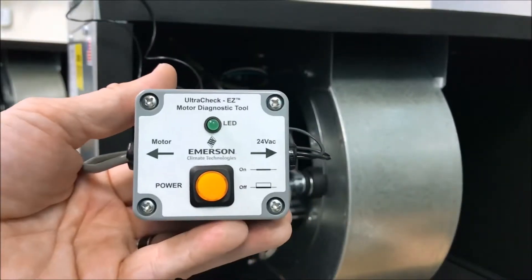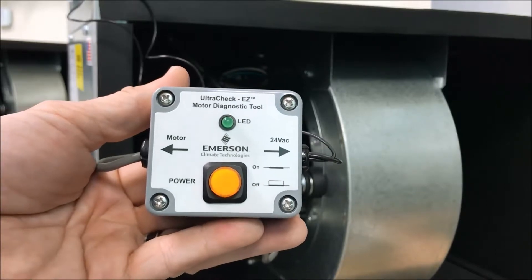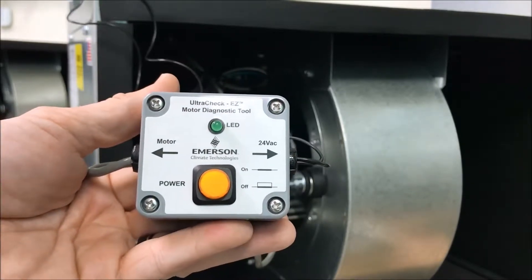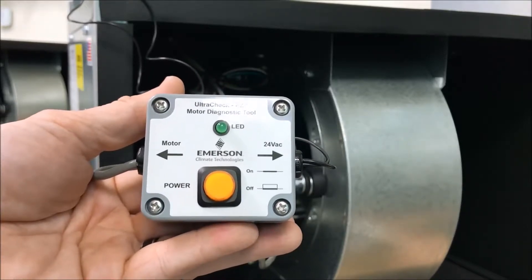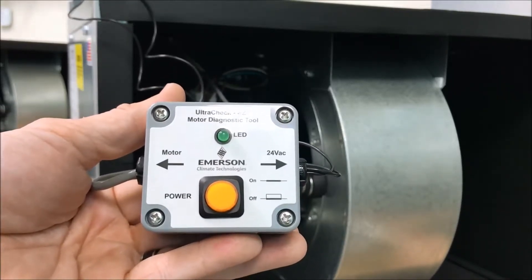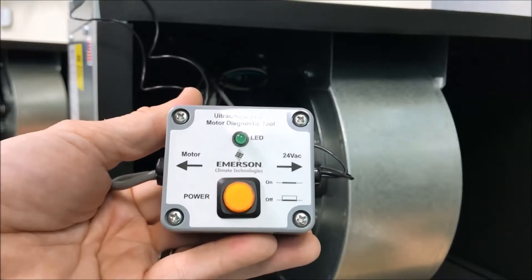The easiest way to determine if your motor is bad is by using this motor tester. This plugs right into the module on the EC motor. It has two wires that go to R and C for 24 volts and it applies 24 volts for a test spin. All you have to do is alligator clips go on R and C.